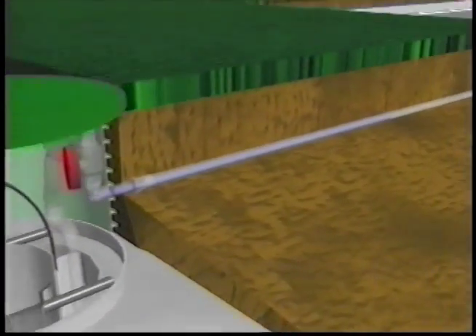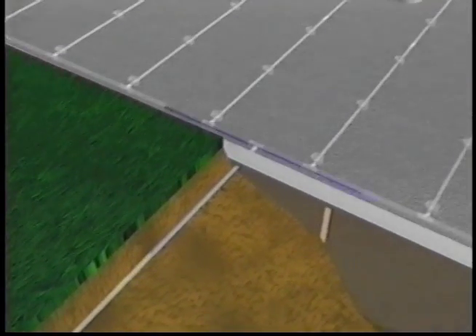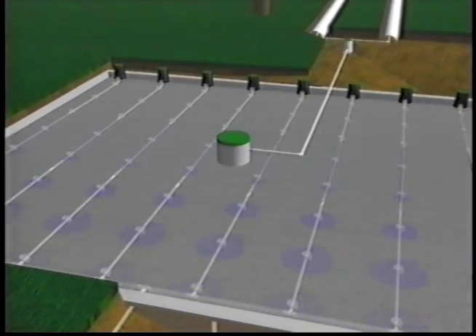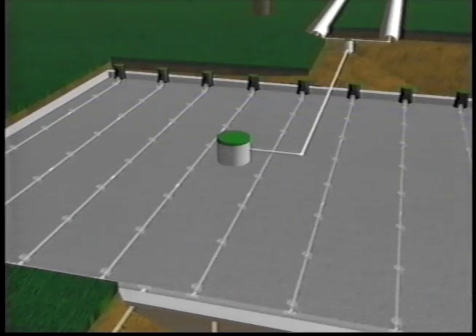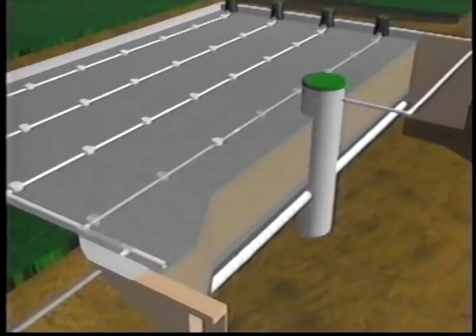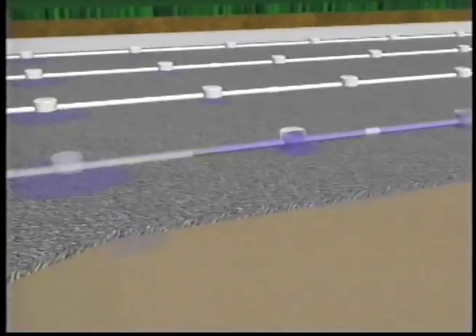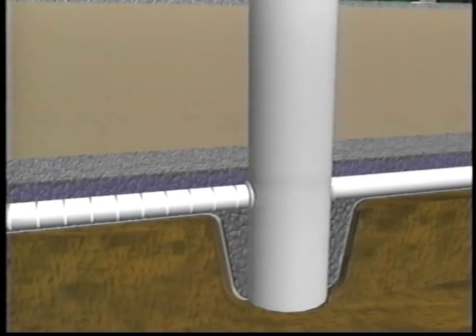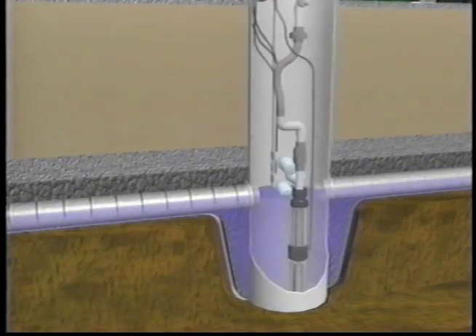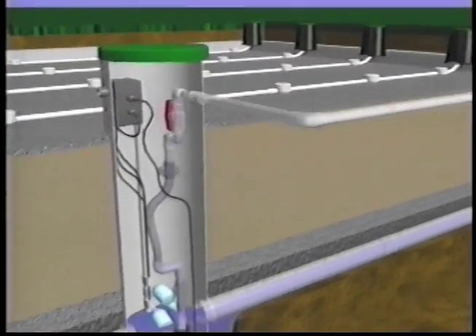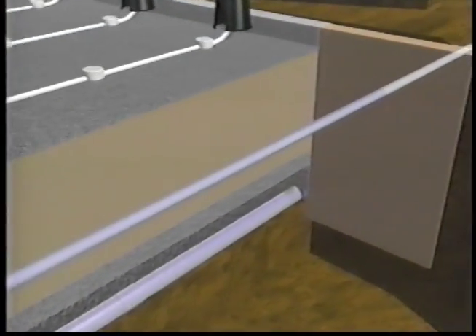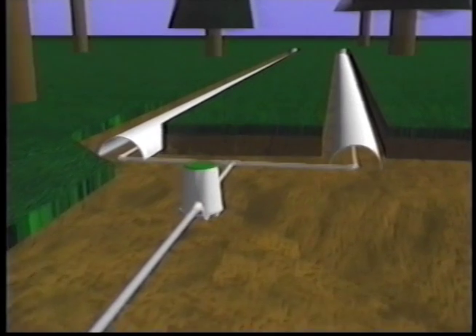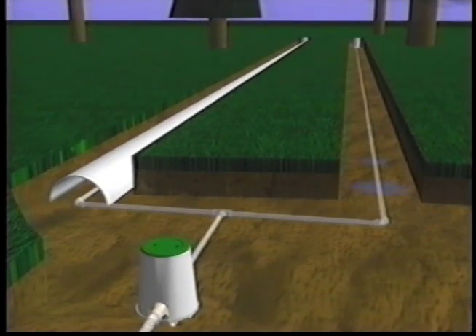It's this effluent that is pumped to the ISF for treatment. The effluent is pumped periodically from the septic tank to the sand filter, where it is dispersed uniformly over the filter's surface through a series of distribution pipes perforated with small, evenly spaced holes. As the effluent trickles down, microorganisms in the layers of gravel and sand break down the pollutants, transforming it into relatively clean water. At the bottom of the filter, this cleaned-up wastewater is collected and pumped to a simplified drain field, where it is discharged through a buried pipe or network of pipes and receives additional treatment from microorganisms in the soil.